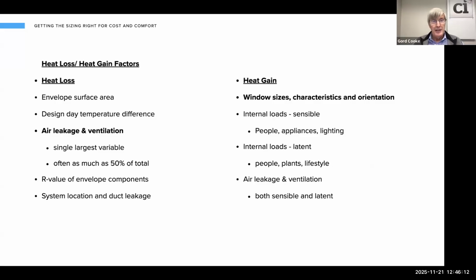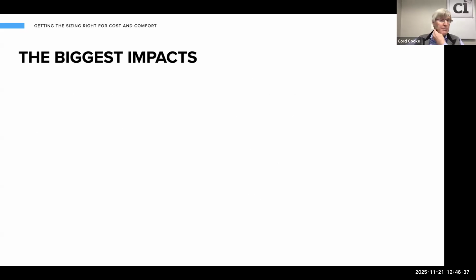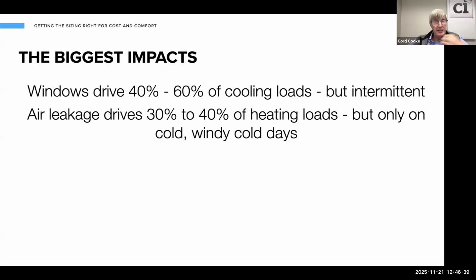On the heat gain side, the biggest component is always the windows. Windows account for between 50 and 60% of air conditioning loads in Connecticut. The size of the heat pump, size of the air conditioner that you need, fully half of that is associated with the glass and which way it's facing. So managing those two loads really helps from a heat pump sizing and comfort perspective. So keep that in mind. And I'll just reiterate again, 40 to 60% of cooling loads associated with windows, 30 to 40% of heating loads, design day heating loads associated with air leakage. And when we get those two right, we're in good shape.